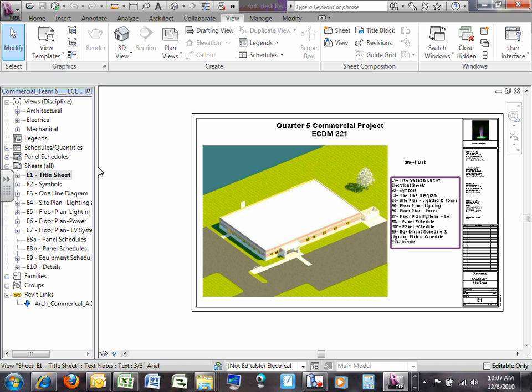We need to power this building with a 208/120 3-phase system. Why? Typical building this size, guys, we wire it with 208/120 3-phase. Why typical? Based on industry practice, engineers. You go to different engineering firms, they might wire it with 480/277. Typically for a smaller building, 15,000 square feet or less, unless it's manufacturing with tons of machines, we power it with 208/120. The alternative is 480/277, which we'll be doing next quarter.